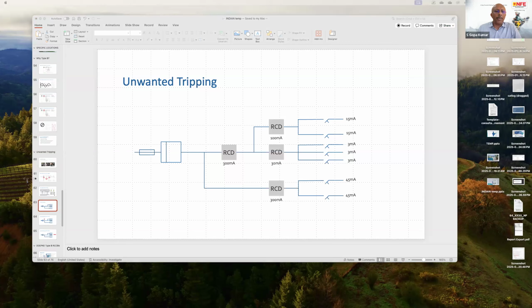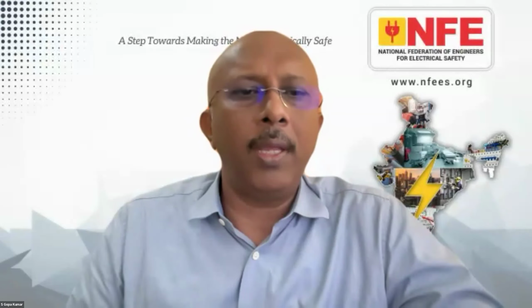So what is the RCCB you used? Is it a 30 milliampere RCCB? 30 milliamps. And these apartments are already occupied, people are already living in them. It is not continuously getting tripped, but when it does, it is simultaneously a few apartments only. There is a leakage in the flat we found, but is there any chance that the source voltage or source power supply variation is the cause? I'm not able to find it.